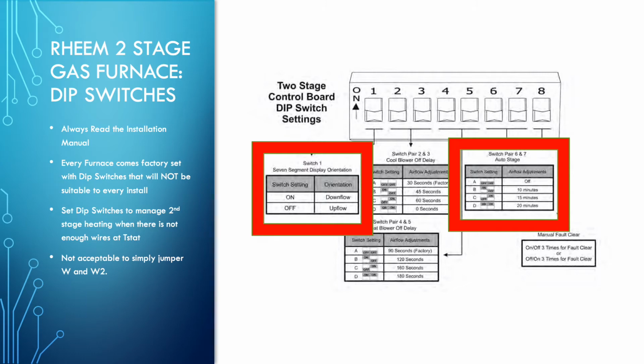there's a thermal limit that can open in the blower compartment when everything shuts off, but it didn't run the blower long enough, so the heat's rising from the secondary and the primary heat exchanger, causing that heat to rise up, trip the limit, and then the system can cycle off and they won't be able to turn it back on right away. Now, typically that's a self-resetting limit inside the Rheem, but some systems actually have a resettable pop switch that, this is different brands, but if that ends up happening, you have to actually get into the blower compartment and reset that switch.